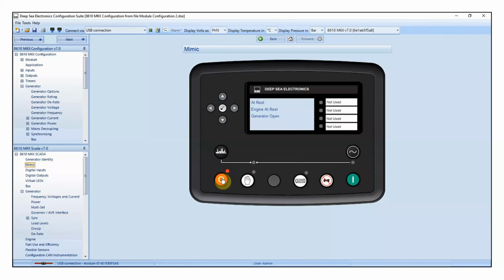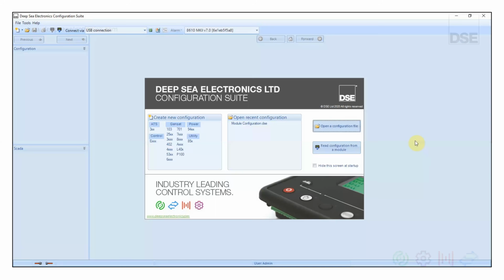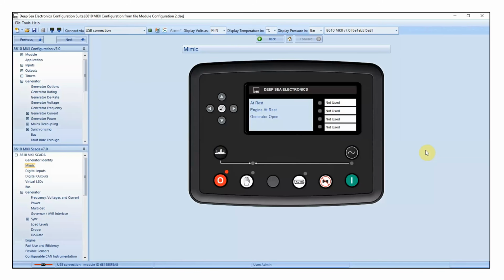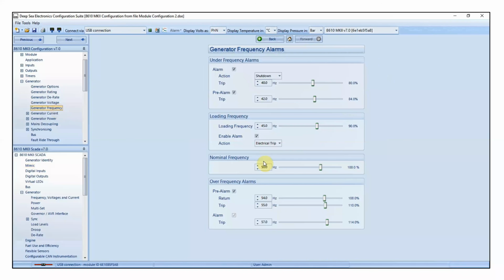Okay, we'll carry on then and start looking at how we do the switch 2 for the governor instead. The switch 2 setup procedure is slightly different. What we're going to do this time, before we even start the generator, is go into the module's configuration and change the nominal frequency. We're going to increase it by 2.5 Hertz, so in my example, that would be 52.5. And then we're going to write that to the controller.